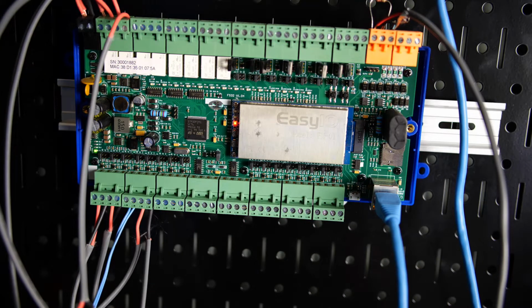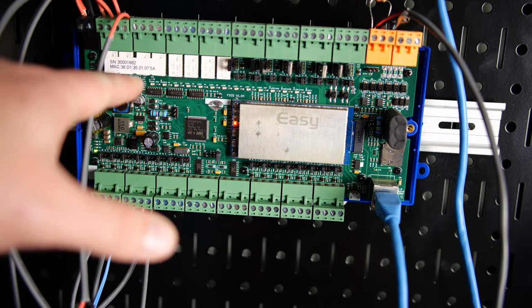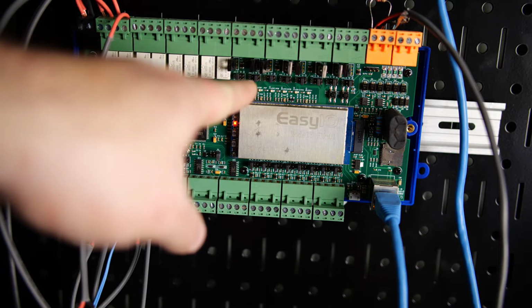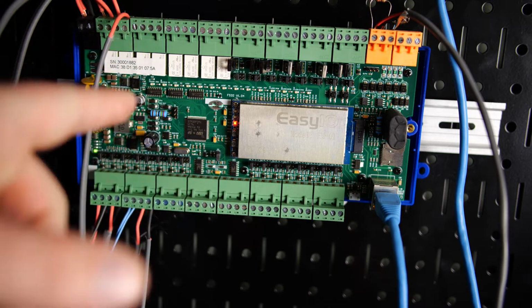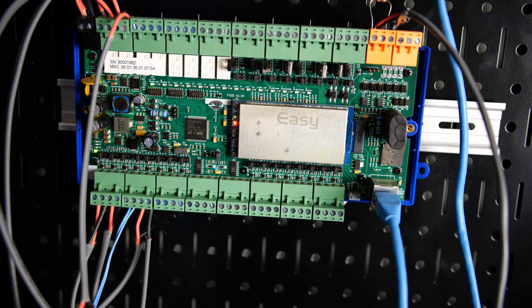First thing we need to talk about is the difference between relay outputs, which you can see right here, and universal outputs, which you can see right over here. Relay outputs have relays built inside, and they can actually open and close contacts to do what's called externally sourced output circuit closing and circuit opening. Basically, we can have voltage that is sourced through our outputs, right? And when this voltage goes into the output, it actually has a relay, and it will open up the relay to stop the voltage from flowing through, or it will close the relay to allow the voltage to source through.